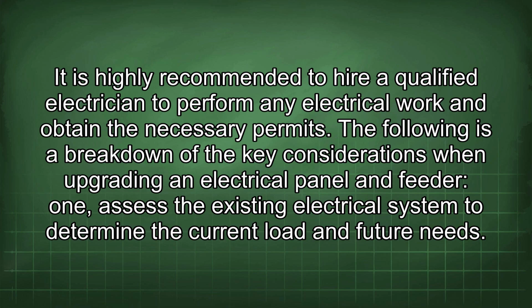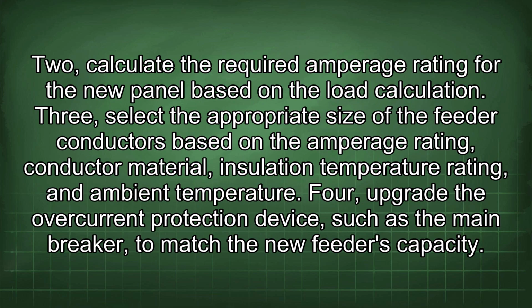1. Assess the existing electrical system to determine the current load and future needs. 2. Calculate the required amperage rating for the new panel based on the load calculation. 3. Select the appropriate size of the feeder conductors based on the amperage rating, conductor material, insulation temperature rating, and ambient temperature. 4. Upgrade the overcurrent protection device, such as the main breaker, to match the new feeder's capacity.